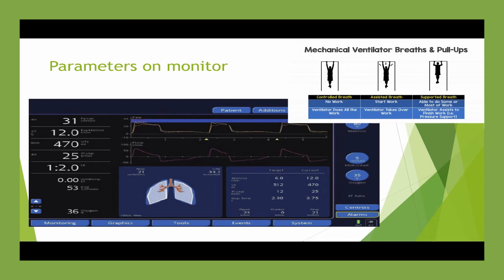In some other cases, in the assisted breath, the patient gives a small peak or indication of breathing, and then the ventilator itself works as an amplifier which supports that signal or mechanical trigger. Then we have the supported mode, where the patient can breathe but in weak phases. So it's like a secondary backup for the breathing mechanism, in order to have safe respiration.